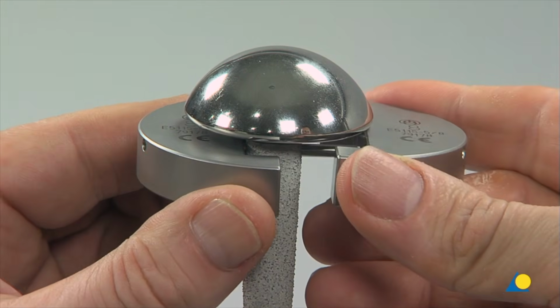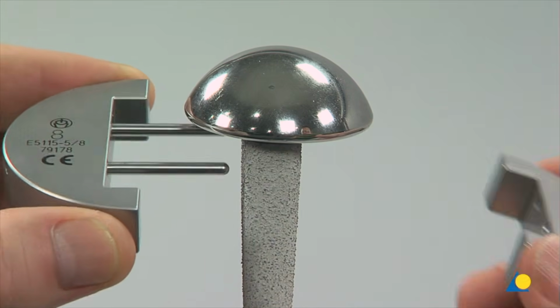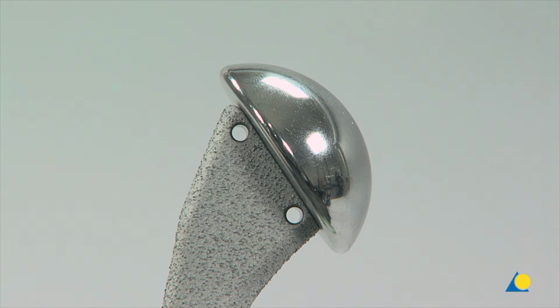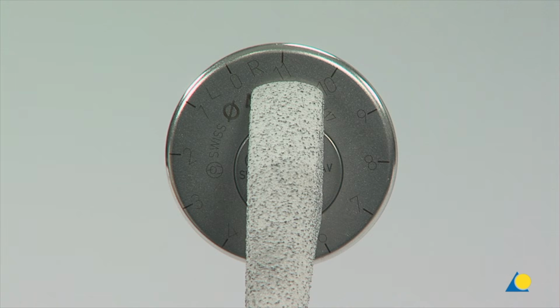The stem holder is removed and the prosthesis is checked for an adequate seating of the head and the eccenter. There must be no visible gap between the base of the head and the stem. The alignment between the head and the stem is also checked.